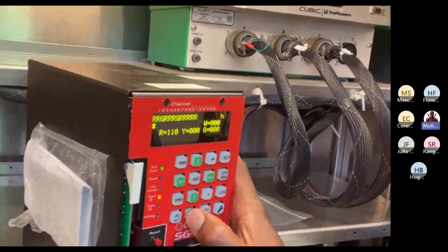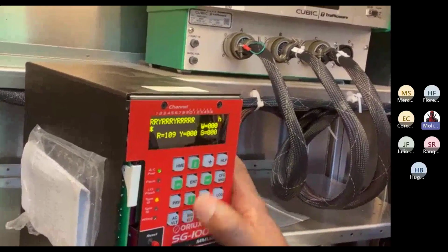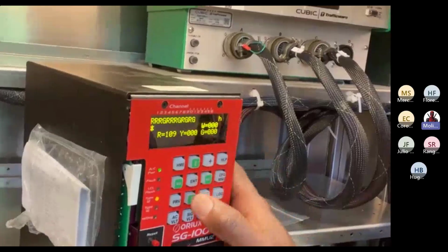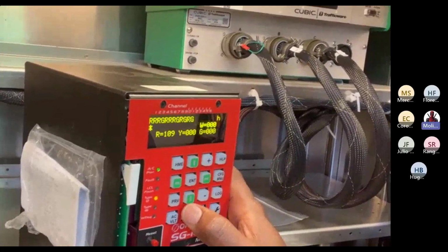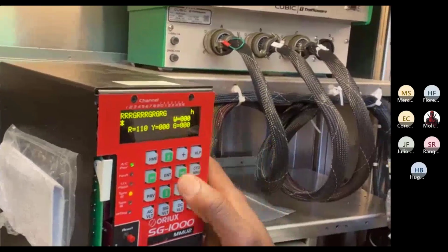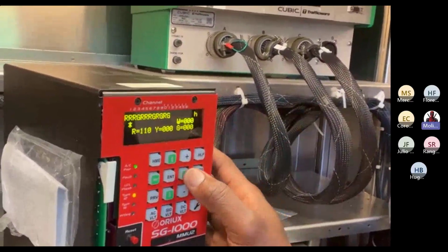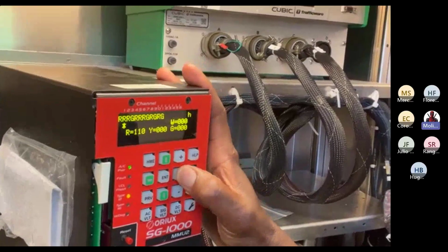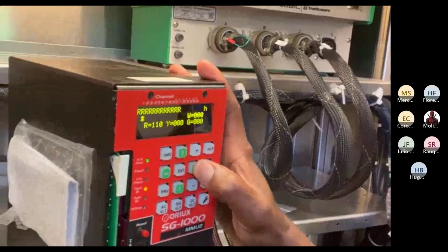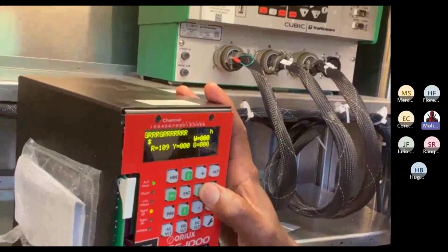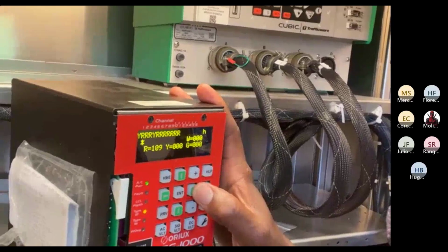Right there, you go. That's green. Right, and that's showing you channel 1. Red is outputting, yellow and green are not. Right, and if you hit the right arrow, see that little star underneath the channel 1 red? So hit the right arrow, and that'll cycle through the channels, and down below it'll show you the real-time voltage outputs on every channel and every output. So if you've got a wire issue, you can find out where that wire issue is.